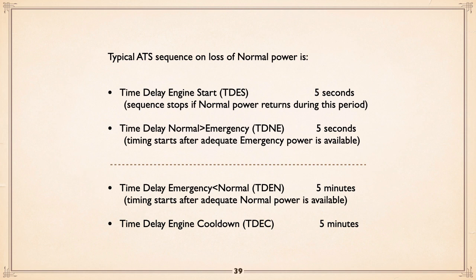Time delay engine start. Next, we're going to transfer from normal utility power to the emergency genset power. And again, there's another 5-second delay. That only happens after the genset is actually up and running, so the timing for the transfer doesn't start until the emergency power is up. So time delay normal to emergency, 5 seconds again. Now we're running on emergency power, okay? And it can last 5 minutes, 5 hours, 5 days, whatever.